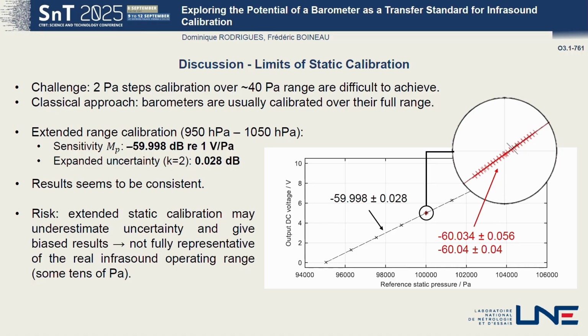So we did it here also. We asked the static pressure lab to calibrate the same barometer but in the full range with a classical approach. You can see here the black points reaching a sensitivity of minus 59.998 dB, slightly different from the one obtained previously, the red data. So there is a small bias. It is covered by the uncertainty, so it is consistent, no problem, but I would like to highlight that there is a risk, specifically when the barometer is not perfectly linear, of having a bias or underestimating the uncertainty with such an approach, because some information is missing when such a classical calibration is provided.